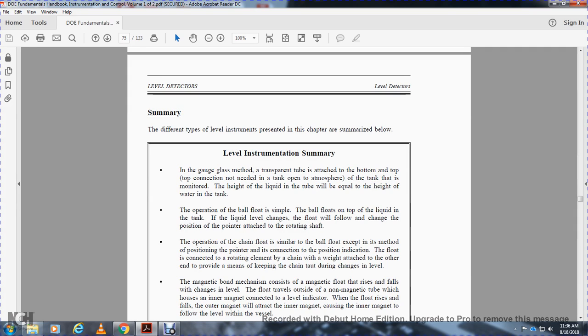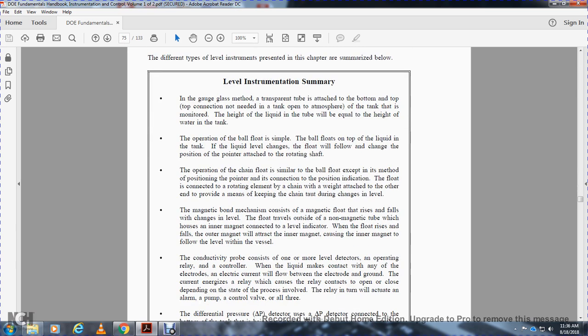The operation of the ball float is simple. The ball floats on top of the liquid in the tank. As the liquid level changes, the float will follow and change the position of the pointer attached to the rotating shaft. The operation of the chain float is similar to the ball float, except for the method of positioning the pointer for the position indication. The float is connected to the rotating element by a chain, with a weight attached to the other end to keep the chain taut during level changes.